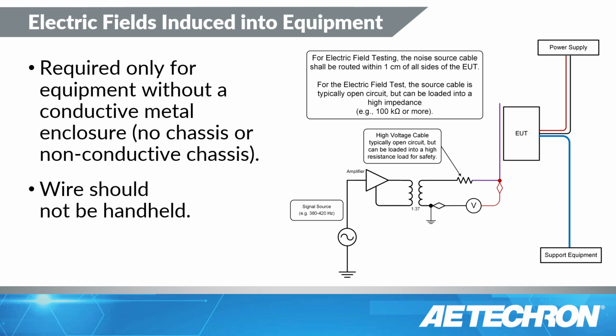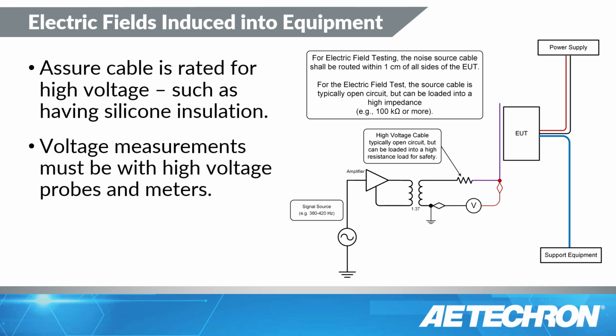This test is not required if you have an all-metal piece of equipment or a well-shielded piece of equipment. This is designed for equipment that has an open chassis or a plastic housing or fiberglass, something of that nature. But if you have an all-metal box, there's no need to do this test. Now, often what I will end up doing is use a silicone insulated wire, and I'll use that also for some of my other high voltage tests, and I'll show you that in a few minutes here. So you want something that's safe and is not going to create an electrical problem.